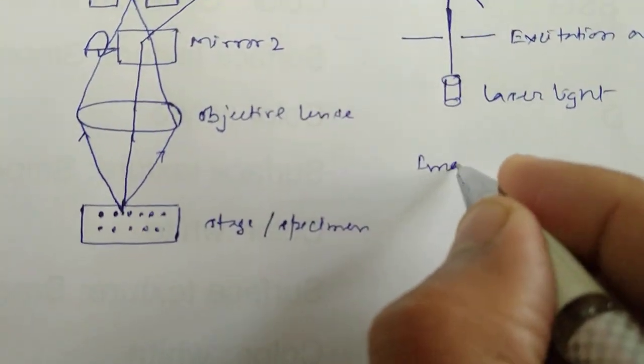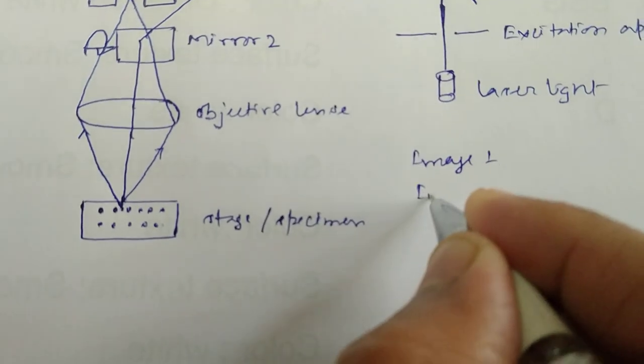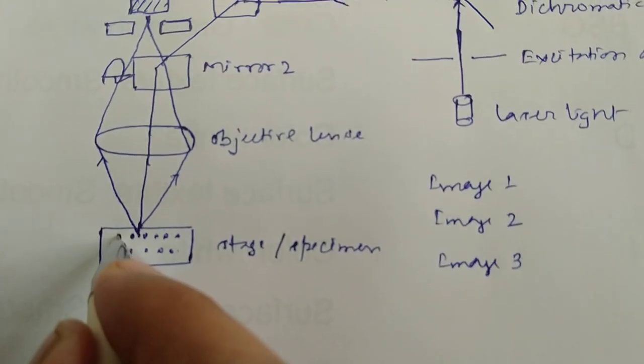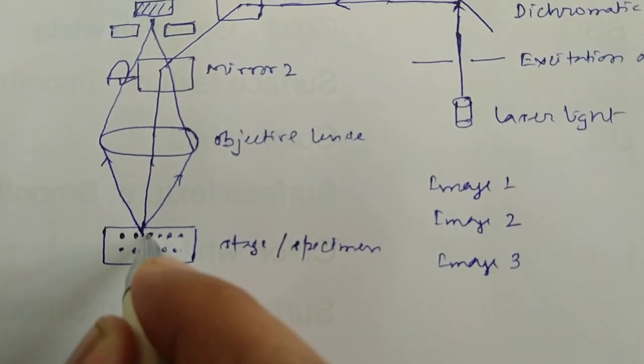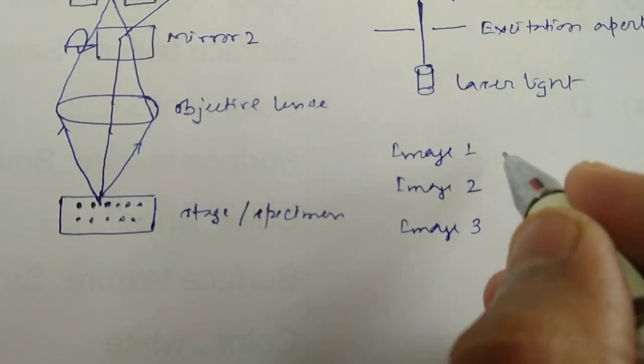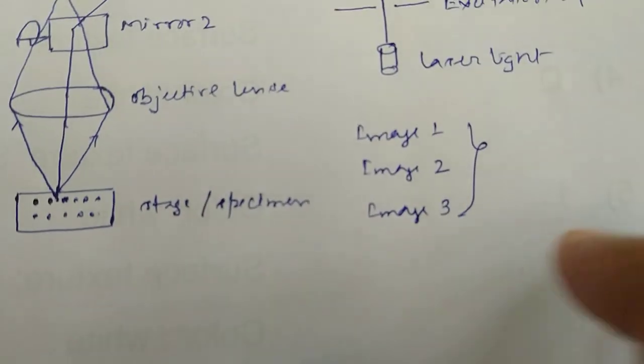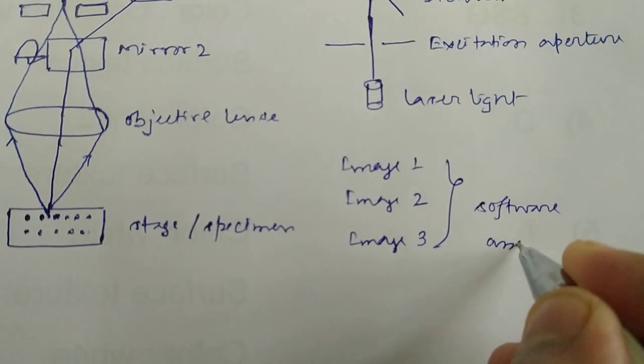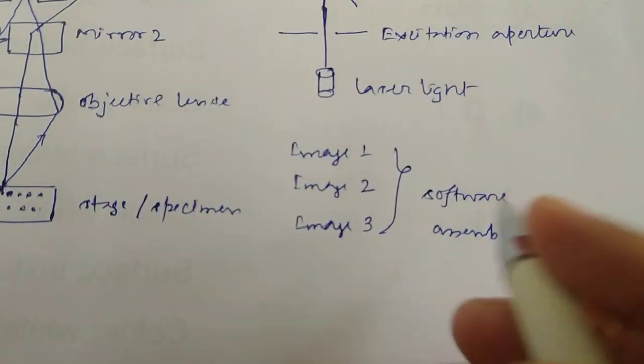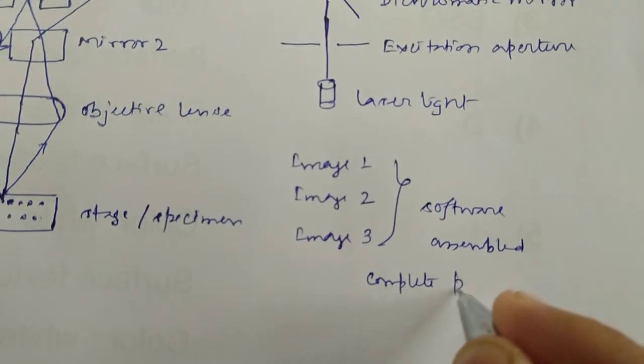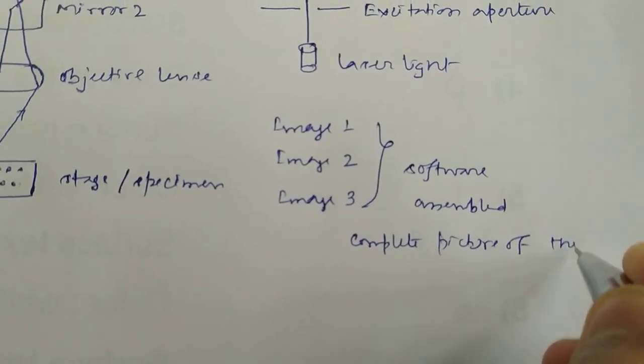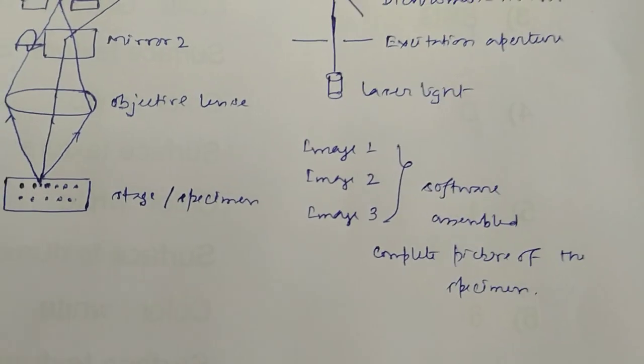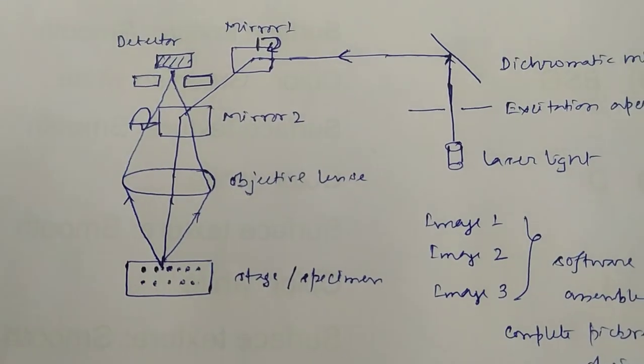The two mirrors can move to different positions so that in-focus light is collected from different points — one light focuses at this point, another light focuses on that point. At a particular time, because one light is coming and focusing on a particular point, the image will be clear. You have several images — image one, image two, image three — each corresponding to a different point. All of these images can be assembled by software, thereby generating a complete picture of the specimen.